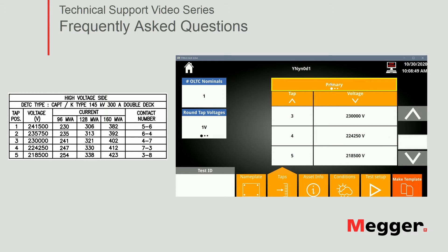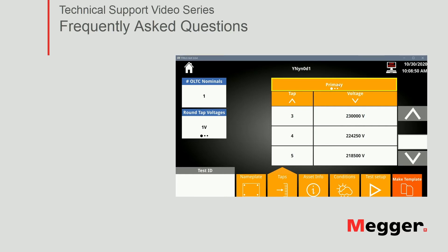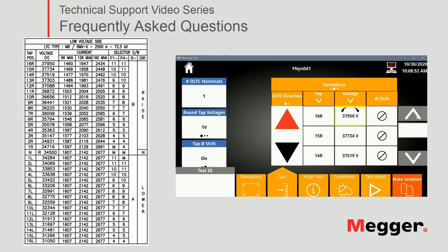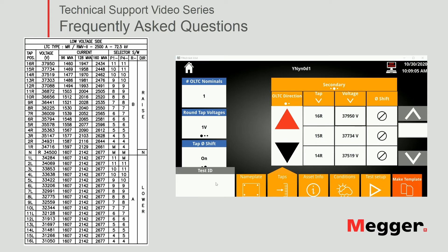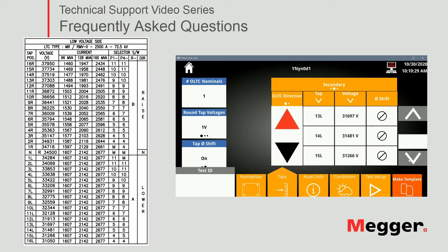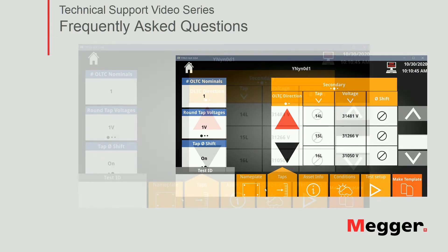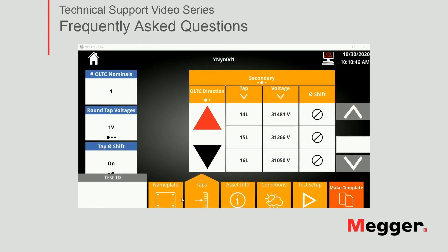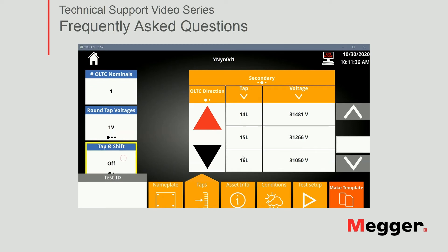I tap on this header to go to the secondary tab, secondary tap changer, my OLTC, and I do the same. Okay, so in this case we're just gonna speed up the video as I check all my tap positions against my nameplate. All right, everything is correct. And I just noticed my tap Ø shift is on so I'm gonna turn that off since we don't need it for this transformer.